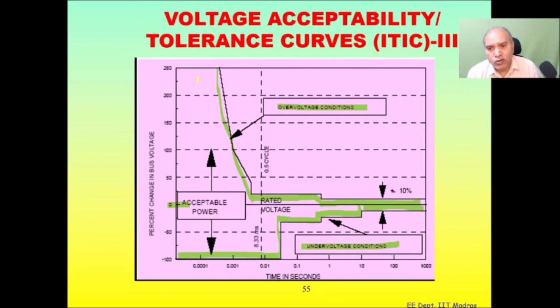A very interesting point is that if the time is very small, let us say 0.0001 second, which basically means 100 microseconds, and this is 10 microseconds, then this is 1 second here. So depending upon that, you can accept a very large voltage, from here to here, for a small time. It basically means that even if you have, let us say, 1000 volts applied to a computer for a short while of 1 microsecond or 10 microseconds, then nothing will happen to the computer.